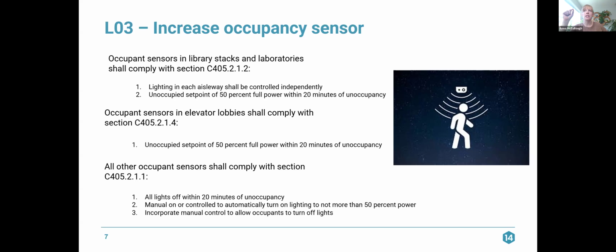The unoccupied set point for each aisleway is going to be 50% of full power, so you're not going completely dark. And that is within 20 minutes of all occupants leaving the space or the aisleway. In elevator lobbies, you have to comply with C405.2.1.4. And so that is just the unoccupied set point of 50% of full power within 20 minutes of all occupants leaving the space. And then all of those other space types that we talked about on the last slide have to comply with the general section for occupancy controls, which is C405.2.1.1. All lights are off within 20 minutes of unoccupancy.